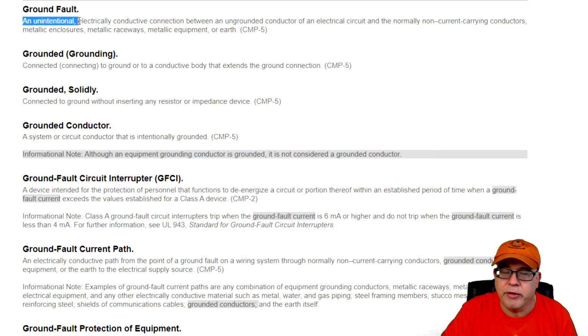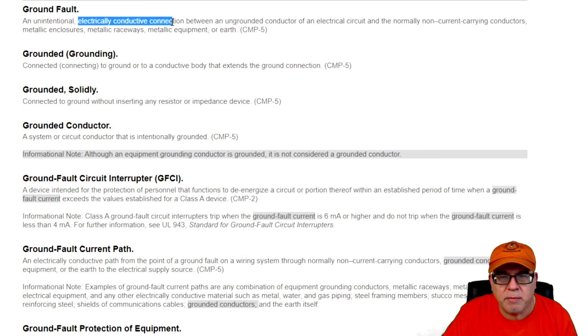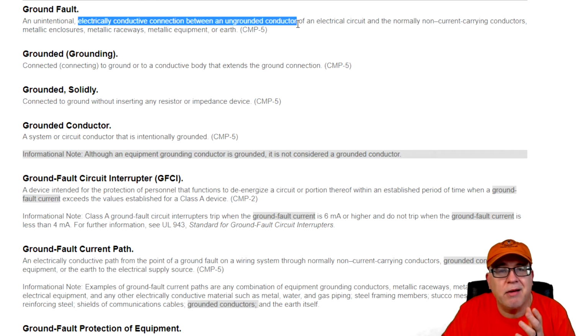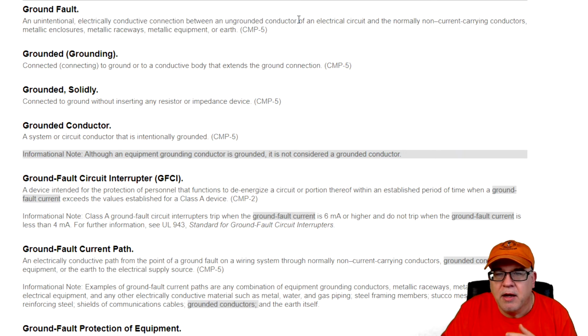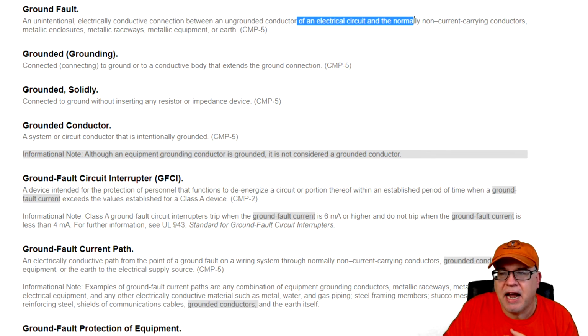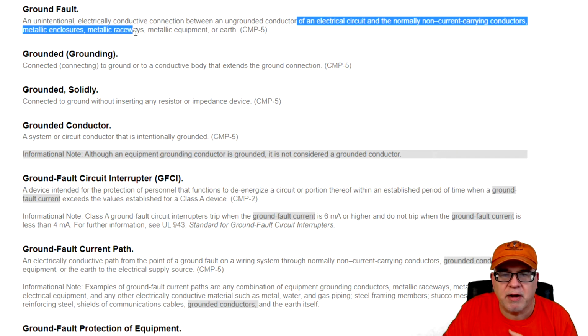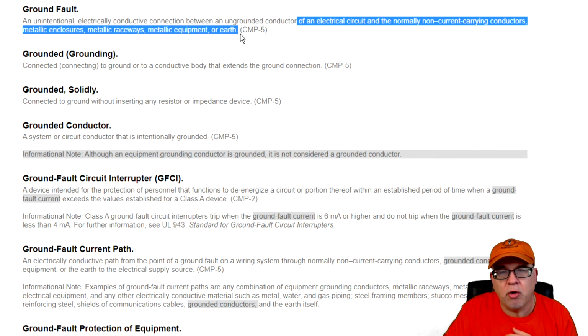unintentional, meaning we didn't try to do it, electrically conductive connection between an ungrounded conductor, like a hot, black, red, blue, whatever, of an electrical circuit, and the normally non-current carrying conductors, metal enclosures, metal raceways, metal equipment, or even earth. So a hot conductor makes an inadvertent contact with the metal raceway, a metal box that's bonded, even earth or anything that's connected to earth can create what's called a ground fault. Okay? So ground fault circuit interrupters, for example, are trying to detect this connection to ground quickly enough. And all of these things are non-current carrying parts.